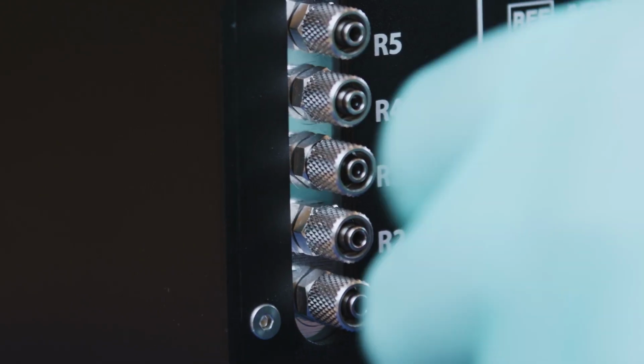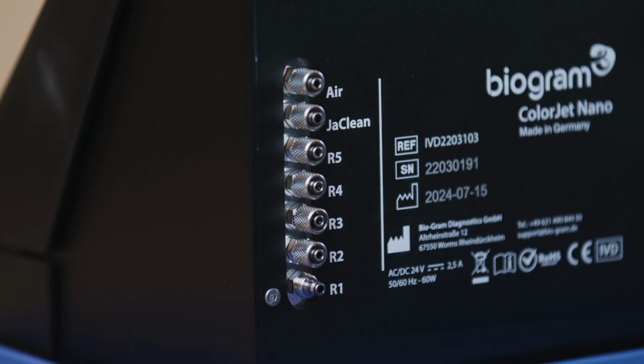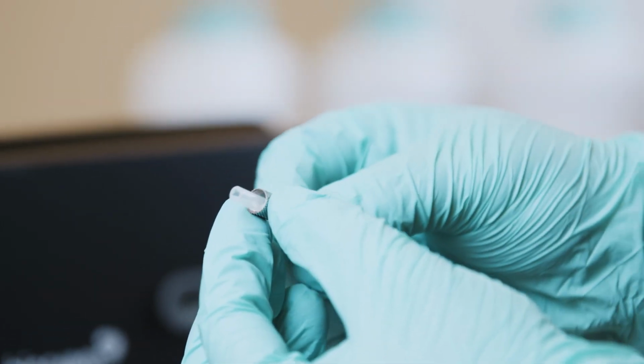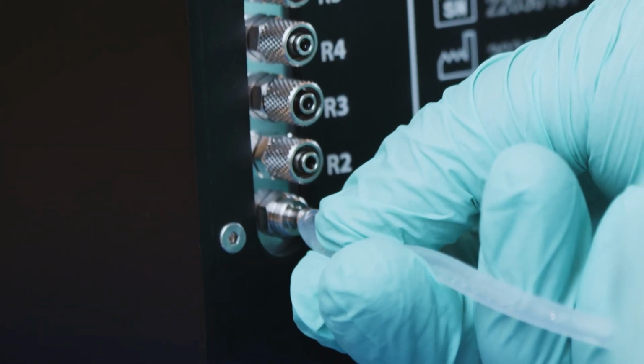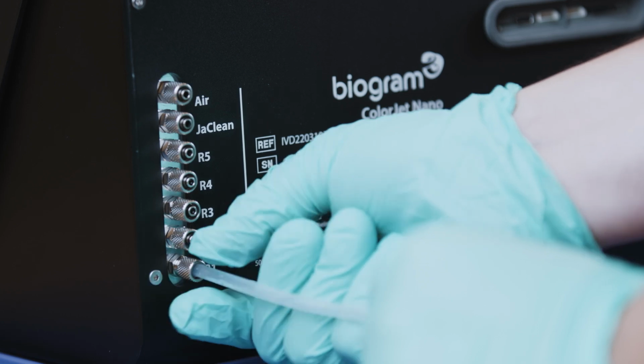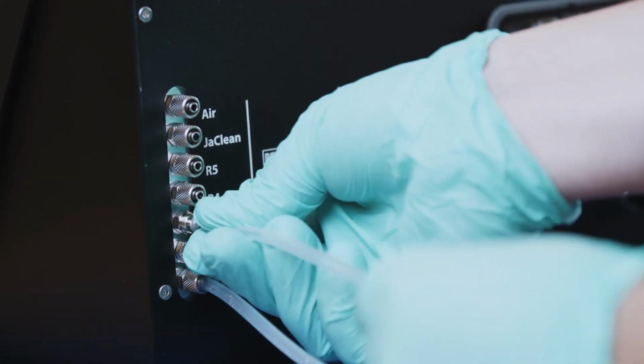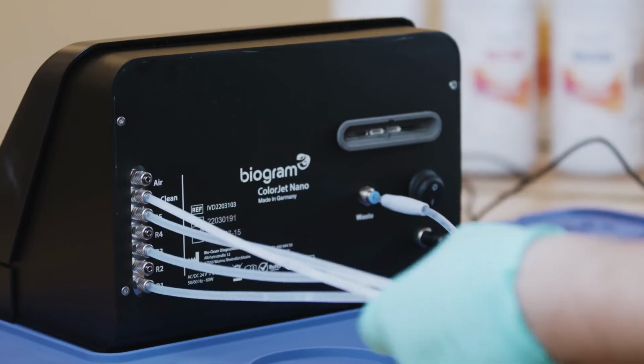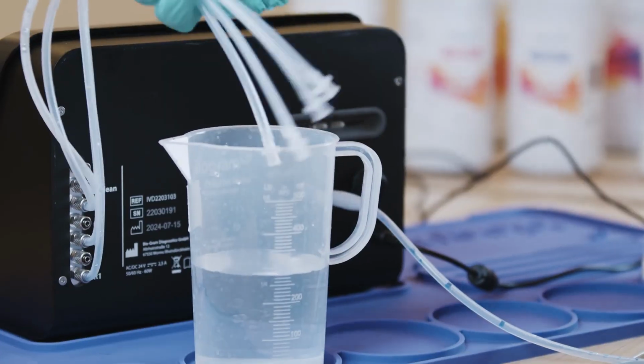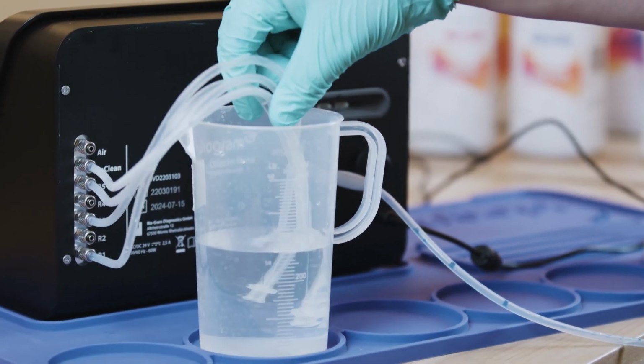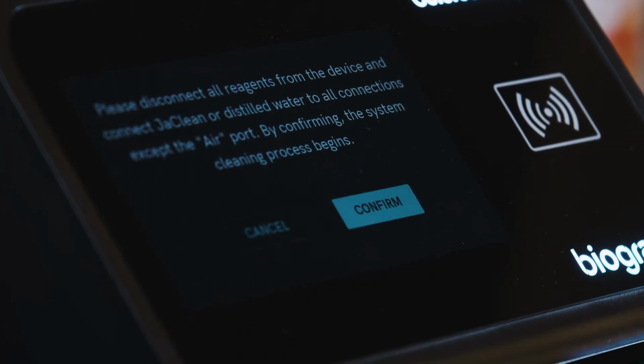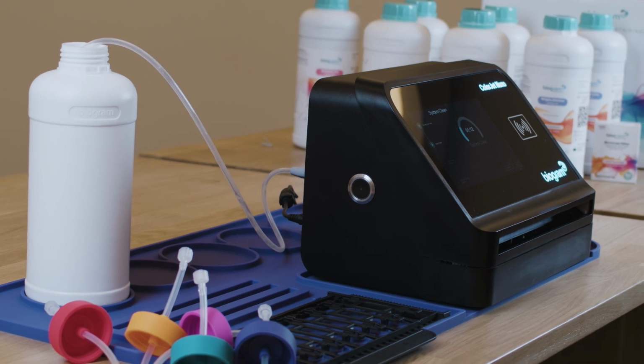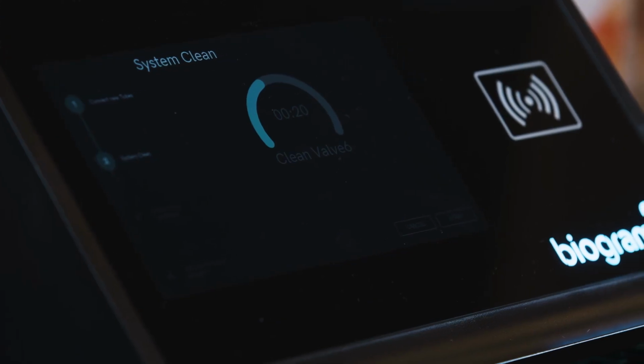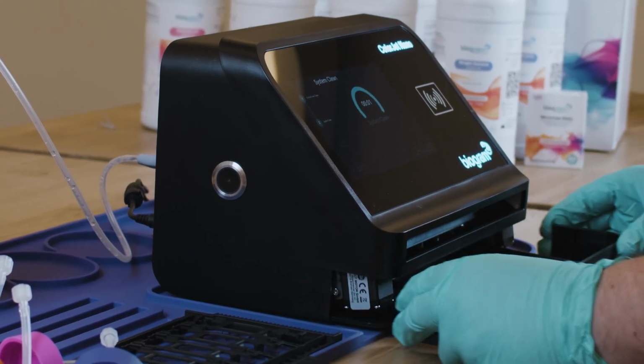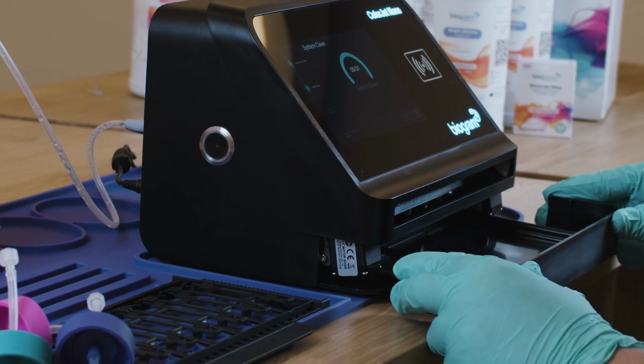Follow the on-screen instructions to connect all tubes to the tube connectors at the back of the device. Always ensure that the air port remains open and unconnected. Fill a container with distilled water, insert the tubes, and start the system cleaning process. Once complete, check the drip drawer for any excess fluids.